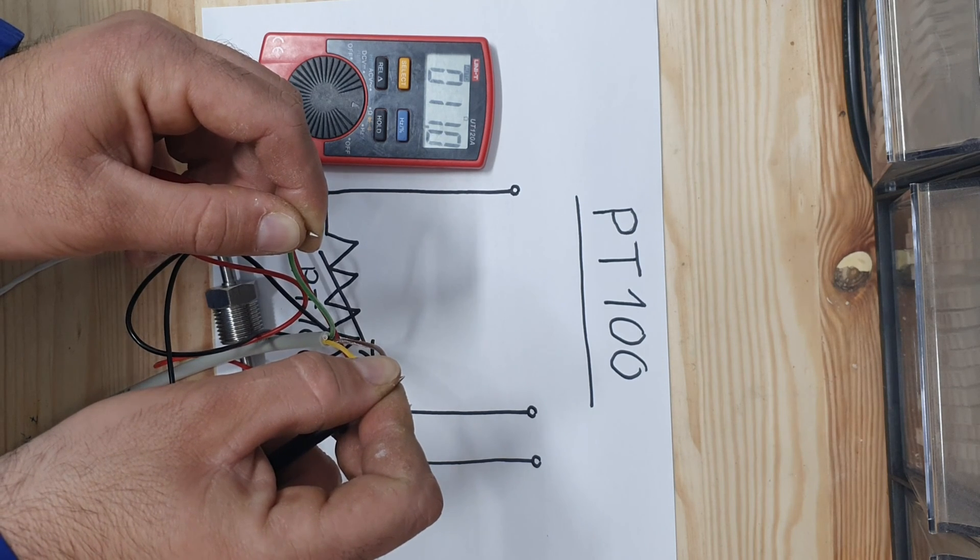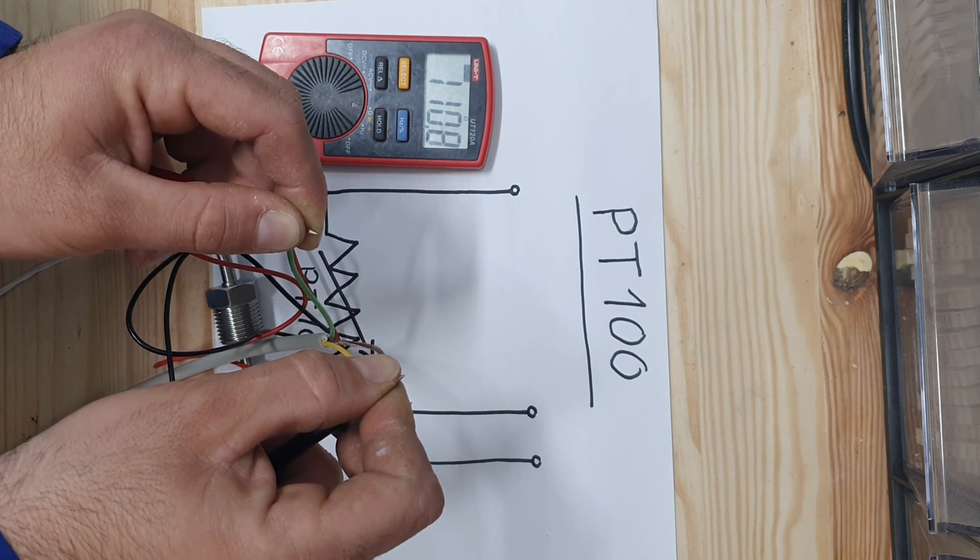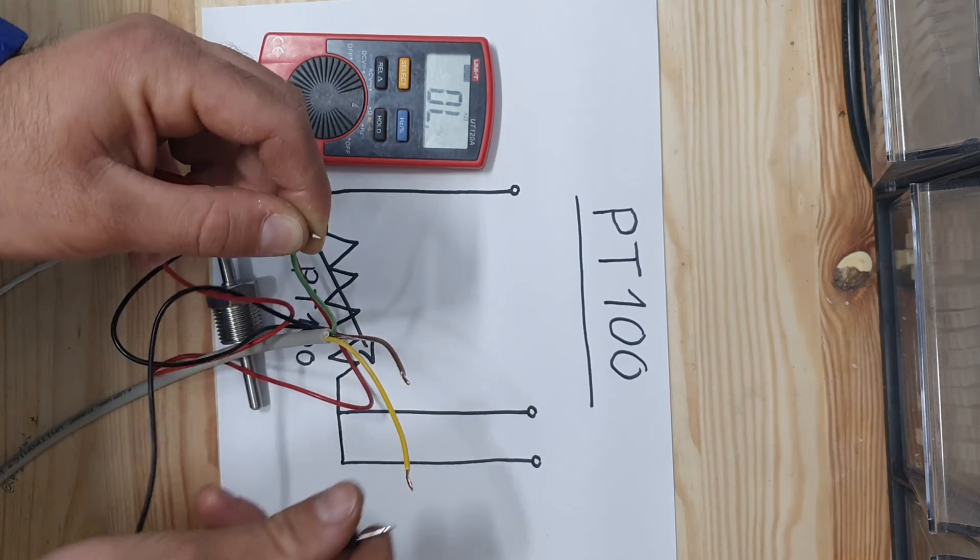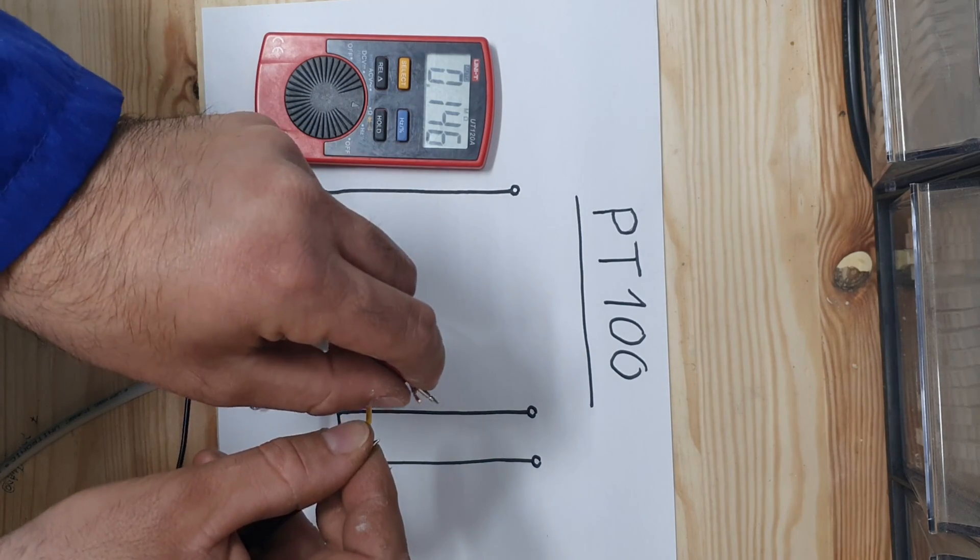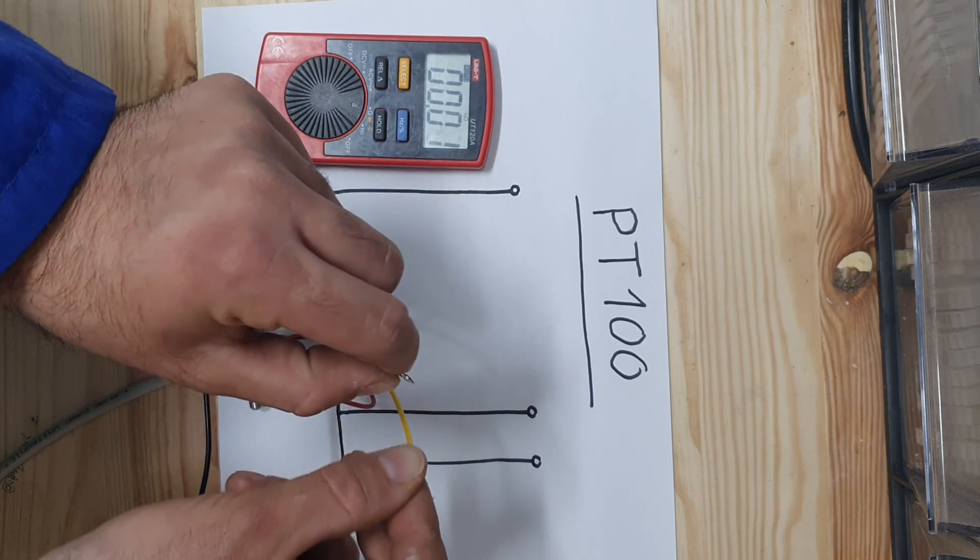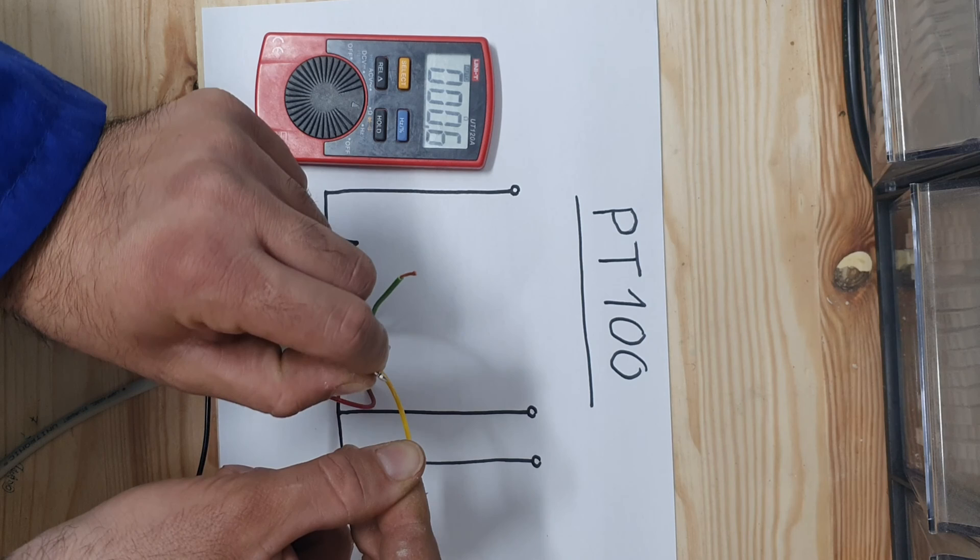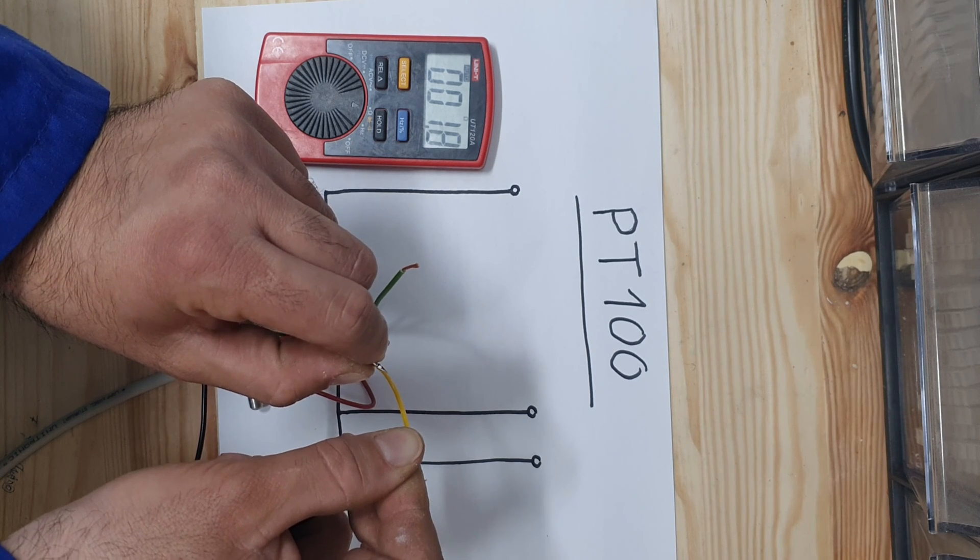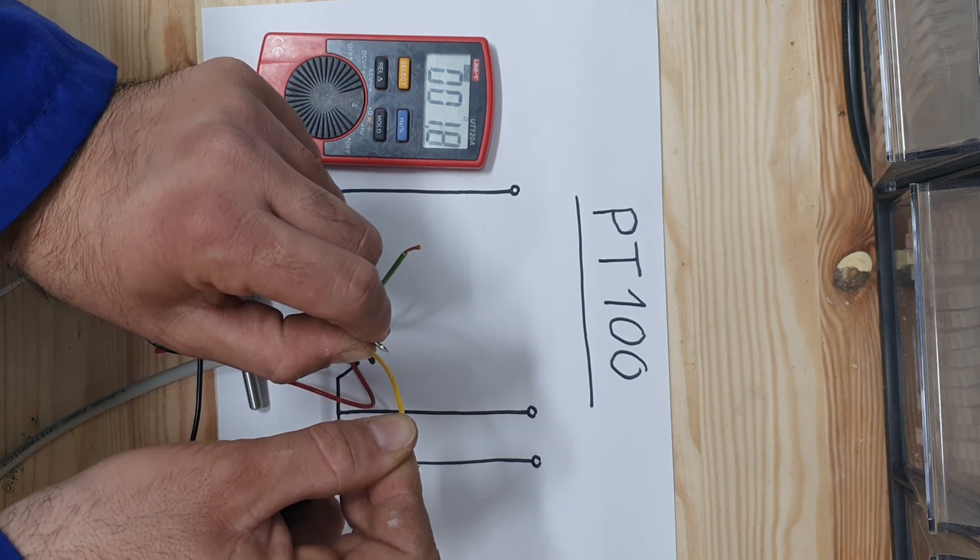If you get a reading close to 100 in two couples, then you know your PT100 and the wires are good. The couple you read zero is the couple of wires on the same side of the resistor.